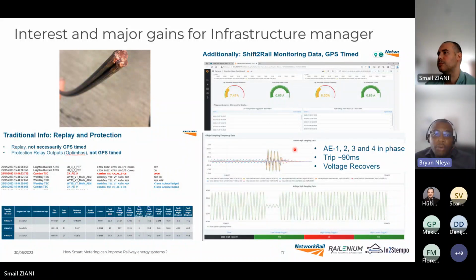On the left, we've got legacy equipment, like the legacy SCADA system, which can still show us when the circuit breakers operated, and we've got the protection relays, which can calculate information as to when the fault occurred and the approximate distance to the fault. But the issue with this equipment is most of it is legacy and bespoke, so it's not easy from an asset manager's point of view to optimize or change if it's not accurate, and in some cases it's not time synchronized.